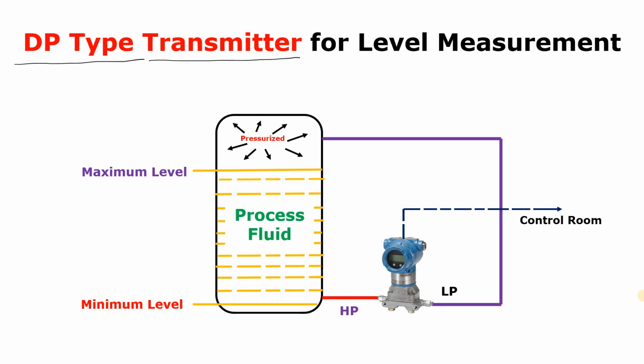When we use the level transmitter, basically whenever our plant is running in auto mode, in process control or advanced process control, we want continuous monitoring of the vessel's level in the control room, like in the DCS panel. We can measure the level by sight glasses or physical glasses, but then we will have to go into the field and check it physically. But if you are in the panel room or control room and want to see the level, you can simply use the transmitter.